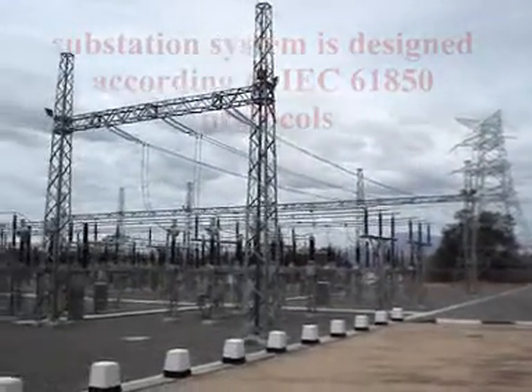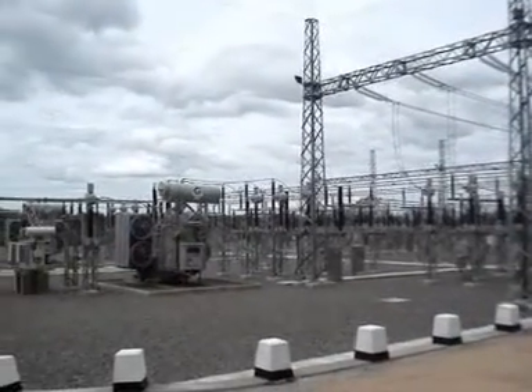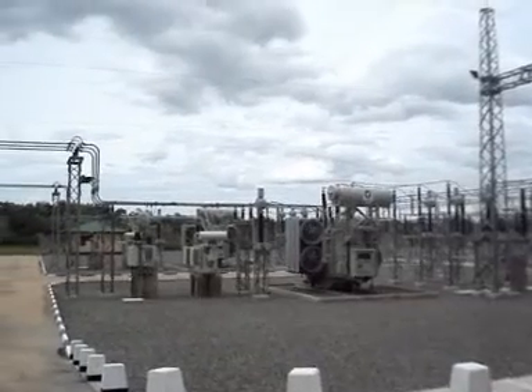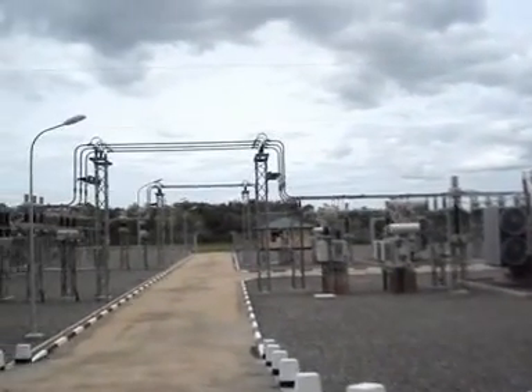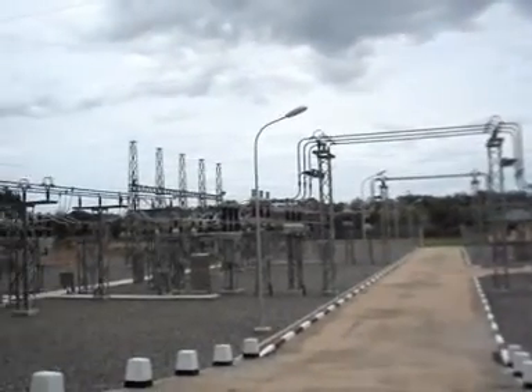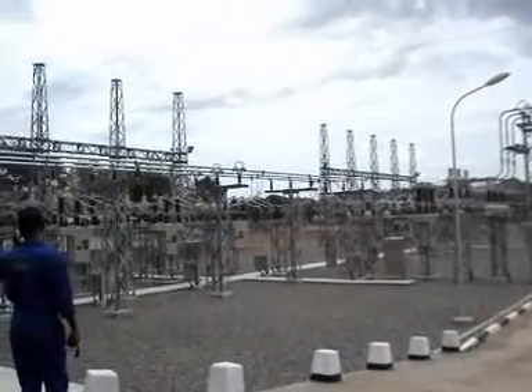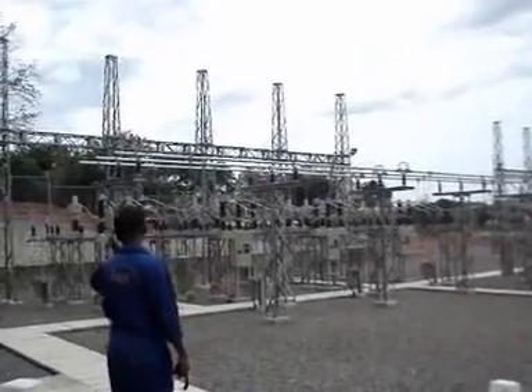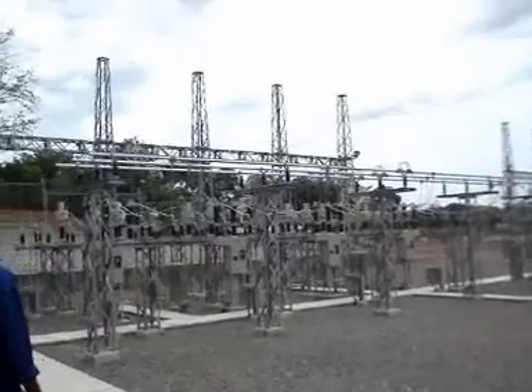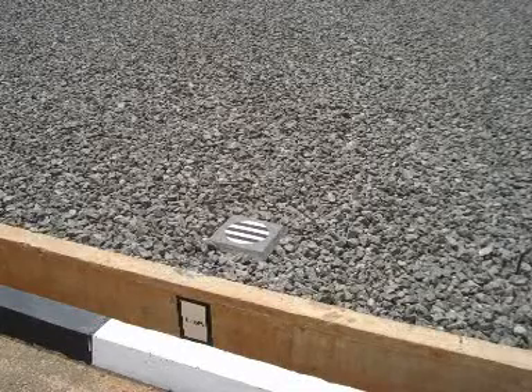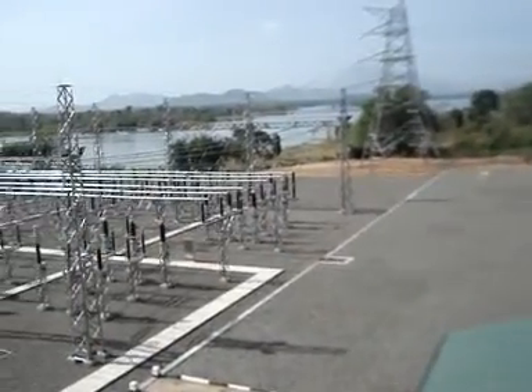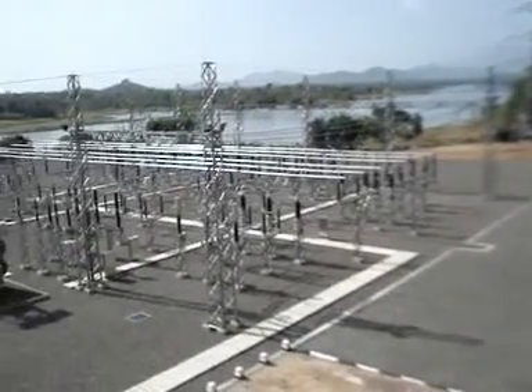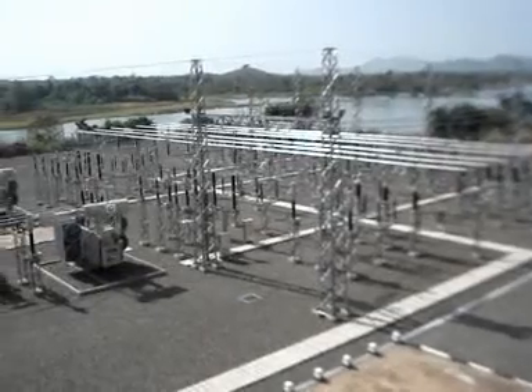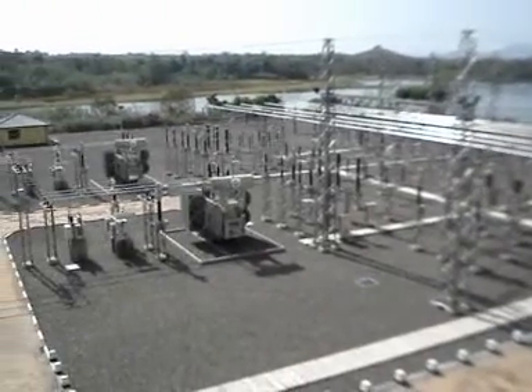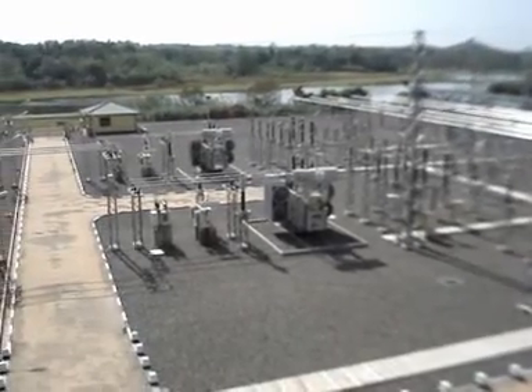The substation automation system, dual, consists of a main operator station and an engineering workstation. One of the station computers operates the system in the online state while the other acts as standby. The standby computer continuously updates and takes over the SA system duties when the main operator station fails. The system is capable of including future extensions too. This substation is proposed to be energized through a newly constructed 21 km long, 132 kV double-circuit transmission line from Rantembe substation to this substation.